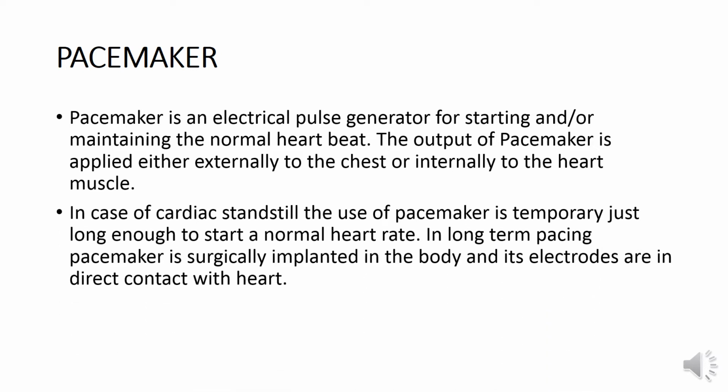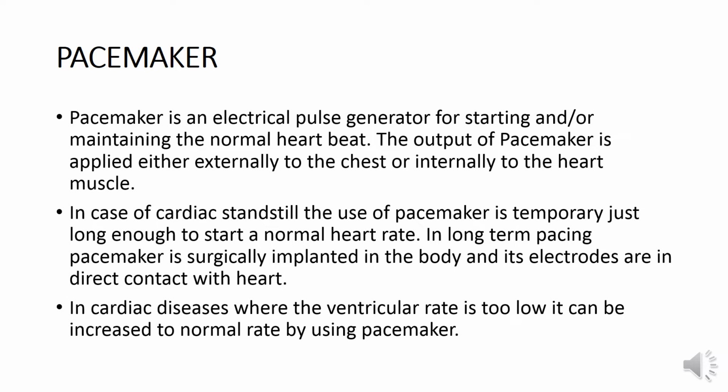In the case of cardiac standstill, the use of pacemaker is temporary, just long enough to start a normal heart rate. A long-term pacemaker is surgically implanted in the body, so the electrodes will be in direct contact with the heart. In cardiac disease where the ventricular rate is too low, it can be increased to the normal rate using this type of pacemaker. This is the pacemaker pulse, which will be generated in the electrical pulse generator.